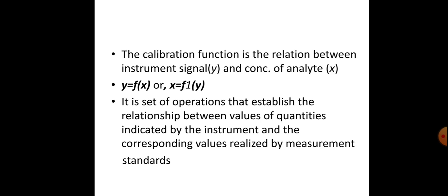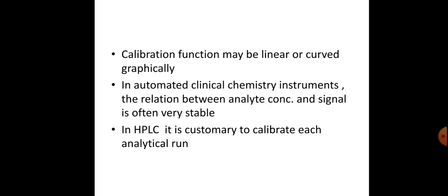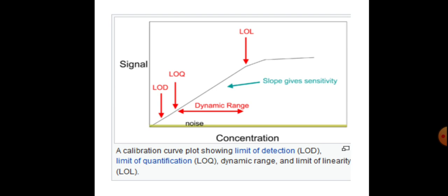It is a set of operations that establish the relationship between values of quantities indicated by the instrument and the corresponding values realized by the measurement standards. So for every test to be accurate, the calibration should be done constantly. The calibration function may be linear or curved graphically. In automated clinical chemistry instruments, the relationship between the analyte concentration and the signal is often very stable. In high performance liquid chromatography, it is customary to calibrate each analytical run. So this is the calibration curve plot showing the limit of detection (LOD), the limit of quantification, the dynamic range, and the limit of linearity. In this calibration curve, the x-axis is the concentration and the y-axis is the signal.